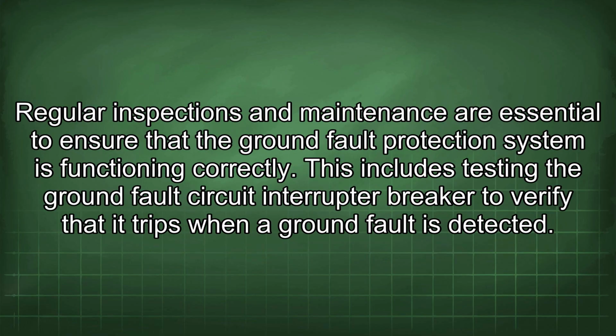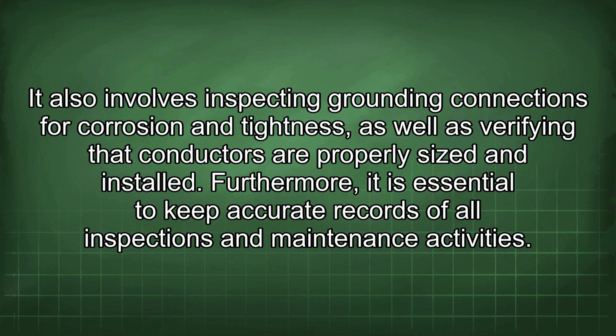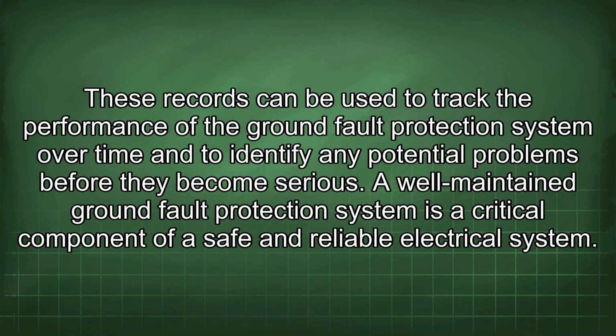Regular inspections and maintenance are essential to ensure that the ground fault protection system is functioning correctly. This includes testing the ground fault circuit interrupter breaker to verify that it trips when a ground fault is detected. It also involves inspecting grounding connections for corrosion and tightness, as well as verifying that conductors are properly sized and installed. Furthermore, it is essential to keep accurate records of all inspections and maintenance activities. These records can be used to track the performance of the ground fault protection system over time and to identify any potential problems before they become serious.